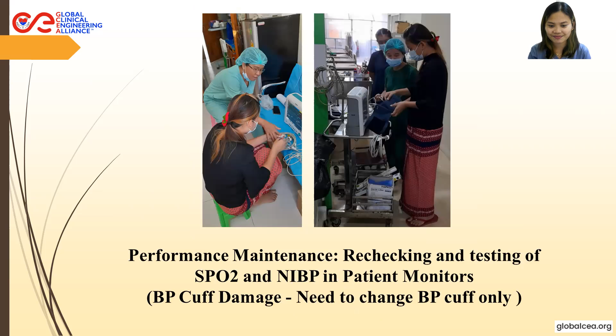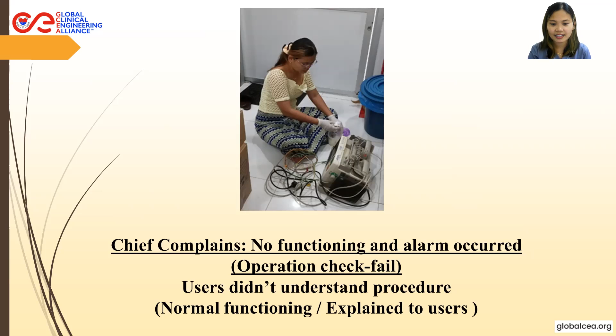Next slide, please. Repaired by our staff. The complaint is that an alarm occurs and the machine is not functioning. After checking it, the operation check failed. The user didn't understand the procedure, so I explained it to the user. And the machine functions normally.